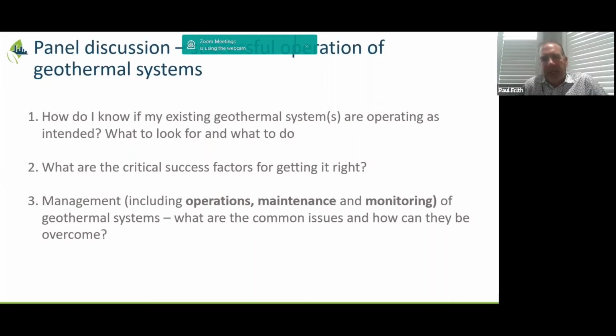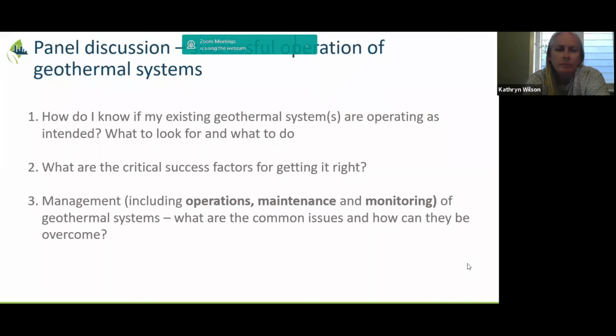One thing I'll add, people may not know this: when it comes to balancing a geothermal system, once it overheats gradually over, say, 2 to 5 years, and you suddenly notice a problem, it's going to take you the same amount of time to get that field rebalanced. If you're not keeping an eye on things over the long term, it will take a long time to fix. That's why keeping an eye on and balancing the systems is so incredibly critical.